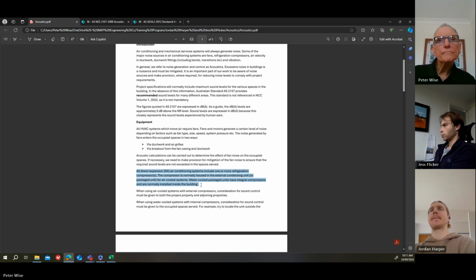So they're commonly used. I guess obviously not as common as air cooled, but water cooled can be very useful for buildings like maybe an educational building where you've got lots of rooms, lots of classrooms, and if the architect or the client doesn't want to see a whole lot of condensers outside the building or on the roof, then you can put in these water cooled package units. But if you have those, you're bringing the compressor into that indoor unit, and the heat rejection is taken away by water, so condenser water. But then you need a cooling tower or a fluid cooler. You've got to find somewhere to put that. But you may have only one cooling tower for the whole project, which serves all of those water-cooled package units, and that can be convenient.